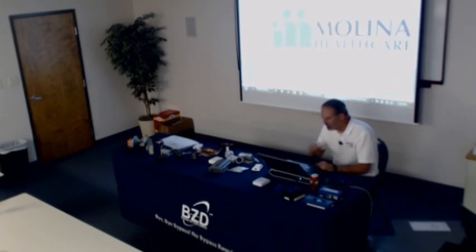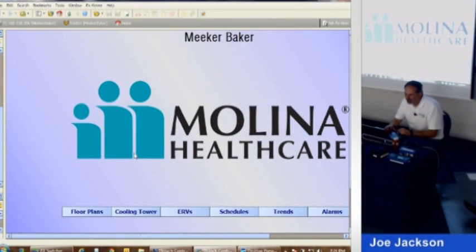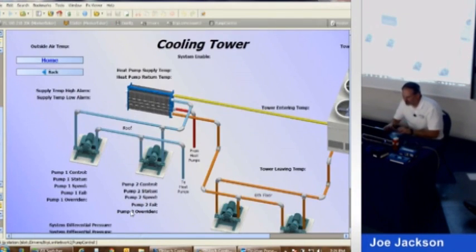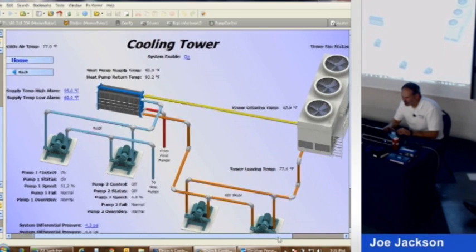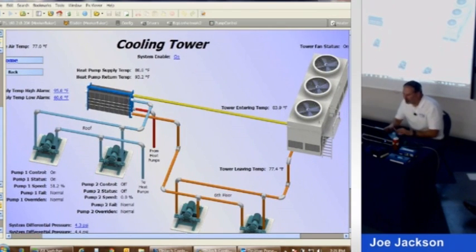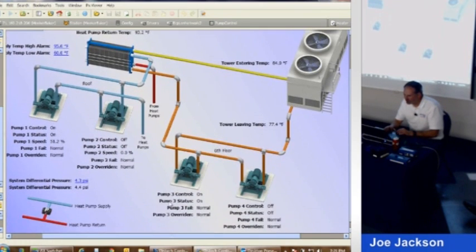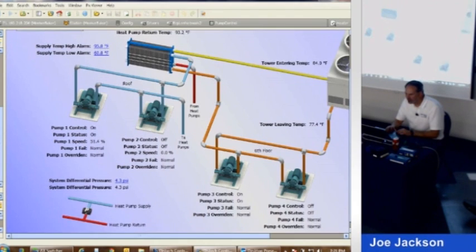So we can go back to home. All the floors look about the same, but we'll jump out and see the cooling tower. This is a heat pump system, so again, I wish we had a little bit bigger screen there, but we can see the tower water going out. We can see if the fans are running. We can see our pump statuses. We got this guy on, this guy off. This is pumping out to the towers. These two pumps are pumping down to the heat pumps. We got a differential pressure transducer, and we're controlling the speed of the pump to maintain 4.3 pounds of differential pressure across the loop, so we got enough water flowing through the heat pumps. Go back home.